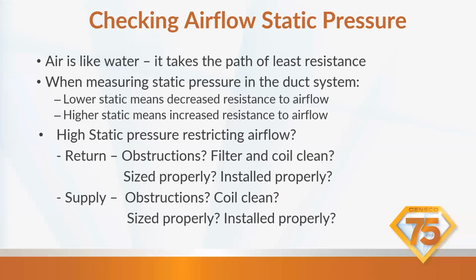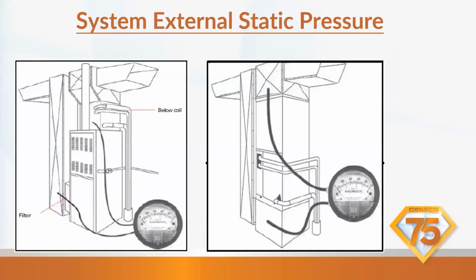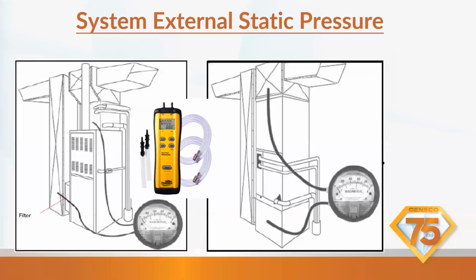If we do not have the correct airflow, it leads to many issues. So keep that in mind. Here's how we take our external static pressure with them. Well, in this one's Magnehelic. There's a manometer. This is a great one. This is the one I use.